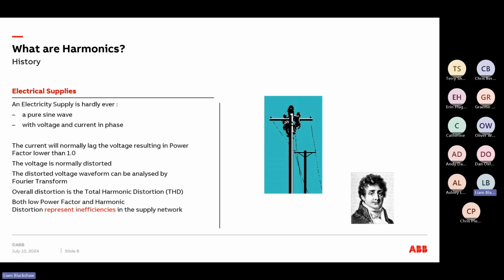The voltage is normally distorted, and what we can say is that a voltage or current waveform can be analysed by what we call Fourier transformation. This all comes back to a mathematician called Joseph Fourier, a French mathematician back in 1700, and you can see his portrait on the right-hand side. He developed the theory behind how we could analyse waveforms using Fourier transformation. When we look at that, we look at the overall distortion, and what we call that is the total harmonic distortion, THD.